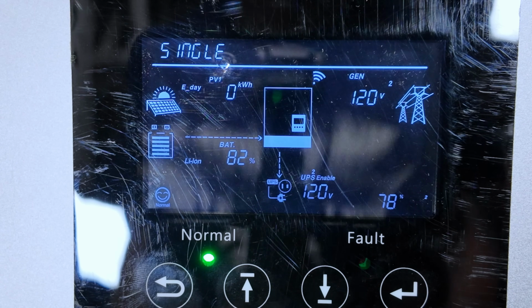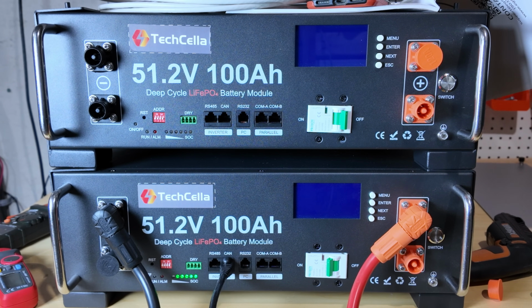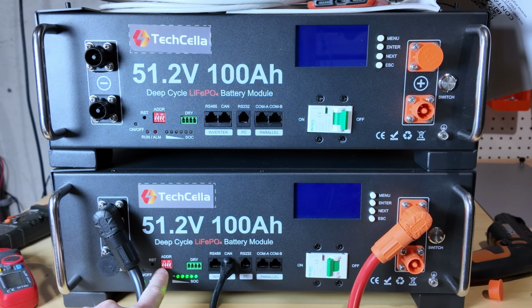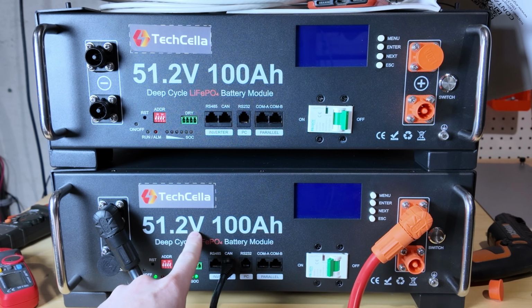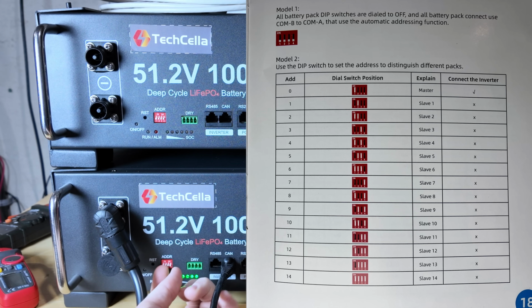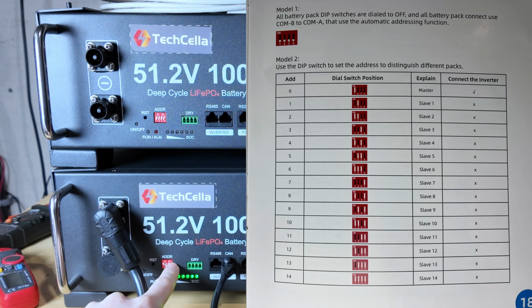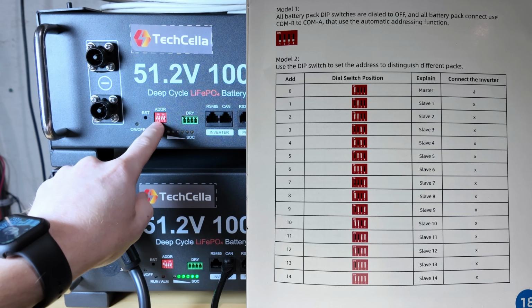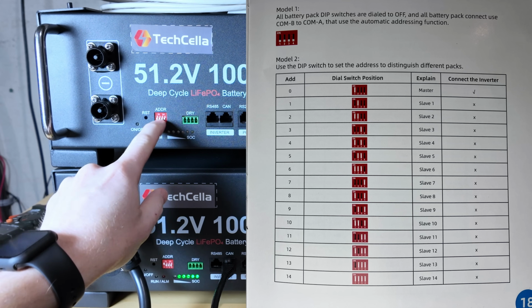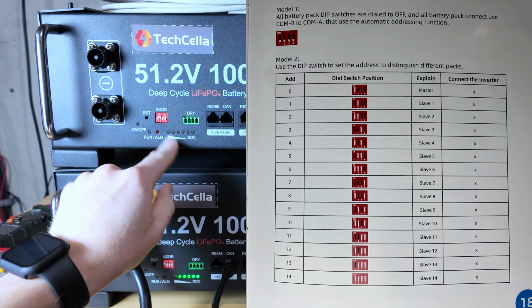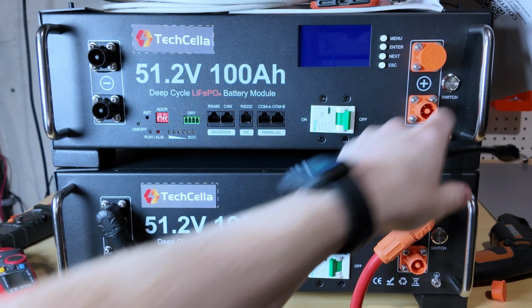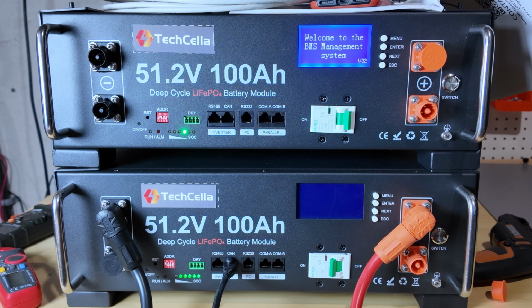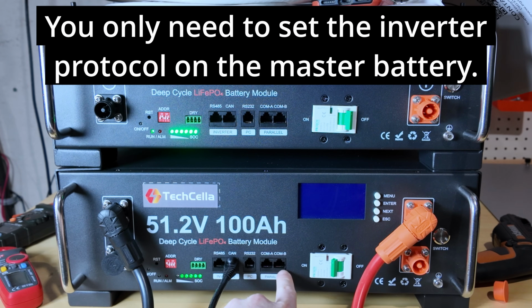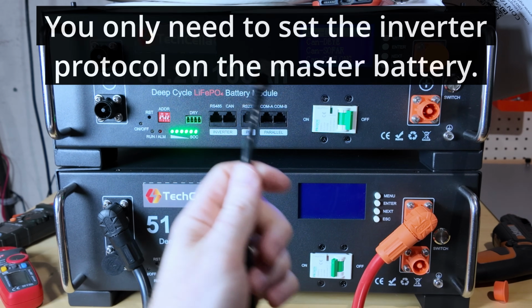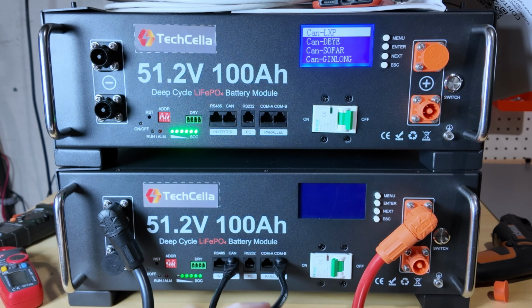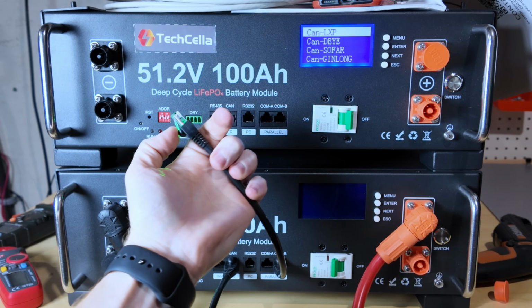Nice and simple. If you wanted to use multiple batteries in parallel, you'll have to set your address switches. For your master battery, set the first dip switch up and all the rest down. For the next battery, first switch down, second switch up, then 3 and 4 down. Turn your BMS on, and go from your master battery, COM B, to the next battery in the string, up to COM A.